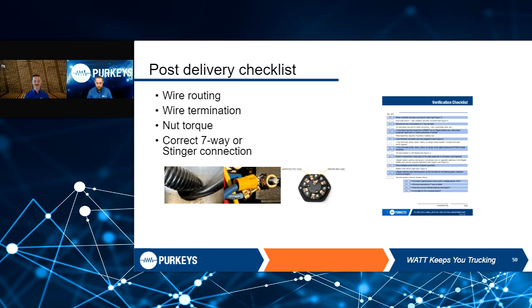Wire termination in that middle picture on the bottom - you really should not be using nylon insulated ring terminals or nylon crimp terminals anywhere at this point. It's 2025, heat shrink is affordable, it's great quality, and you can see the quality of the crimp underneath. You should really be using uninsulated wire terminals and then sliding heat shrink over it. That way you can visually see that the crimp was made properly and the wires were inserted all the way. Nylon crimp terminals really should be retired altogether.